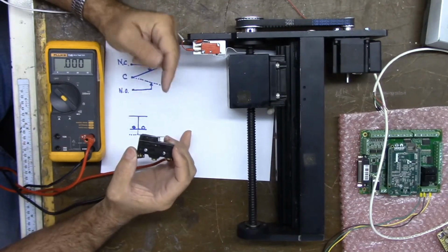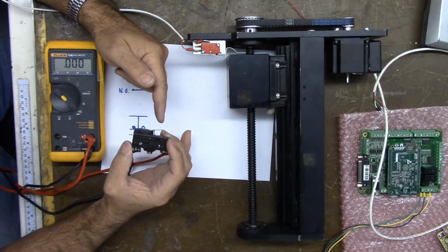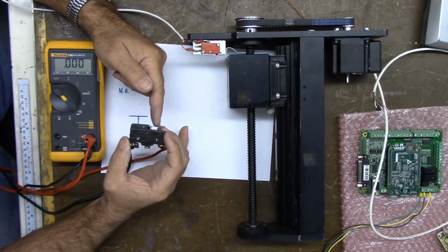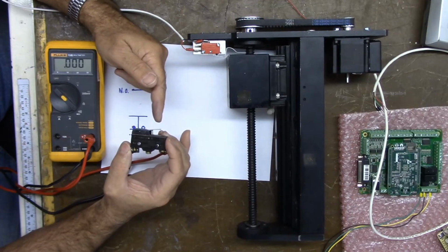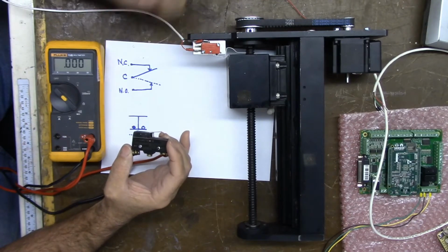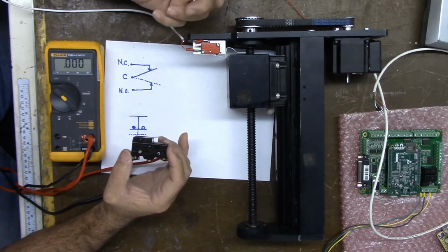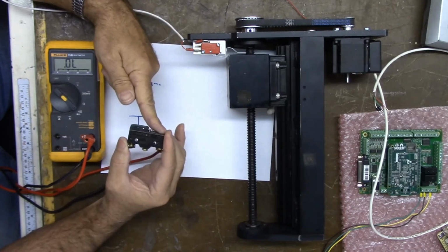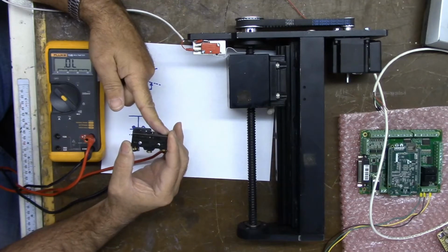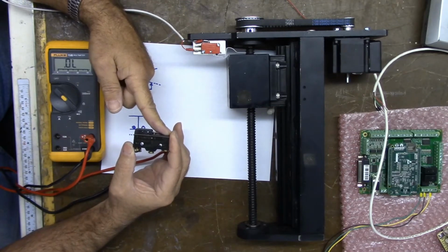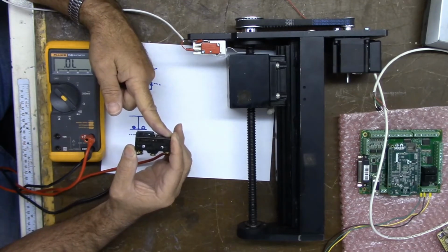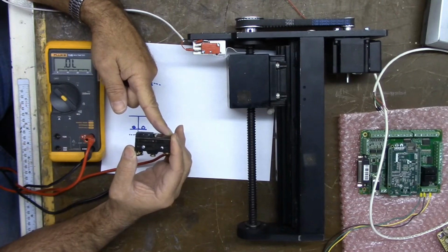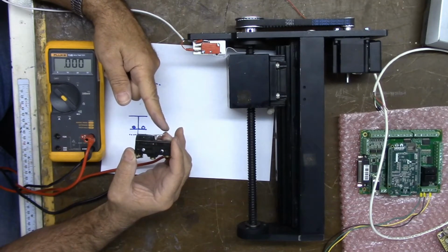Now when you home your machine, the tool is moving towards the switch, it hits it, Acorn sees an open circuit, it backs off. Home is set. Now, in the not so good scenario, where there's something wrong and you have a runaway, your machine tool hits the switch, Acorn sees an opening and immediately stops, says limit switch tripped, and you have to back off that switch until the circuit's closed again.